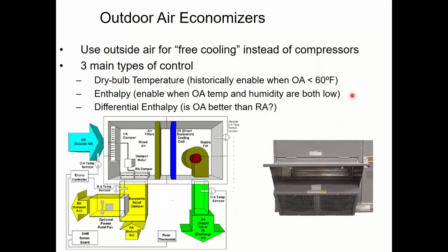Now, the problem is sometimes I have temperature that's cool, but it's also rainy and humid. I don't want that. That's not good. So I can take a step up and go from a dry bulb economizer to what's called an enthalpy economizer. Enthalpy, if you don't know, is the sensible plus the latent energy. We'll talk about that more next week as well. But for right now, just consider it to be temperature and humidity. If the temperature is low and the humidity is low, go ahead and use the economizer for free cooling. The third way I can do it is differential enthalpy.